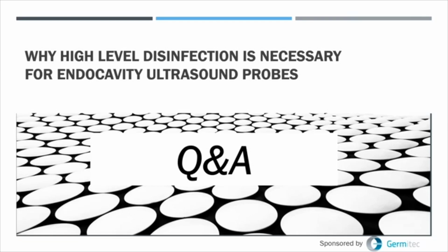The way those studies are done looking at probe covers, there are a variety of techniques one can use. One would be, if it's something like a condom cover, just take it off. You can fill it with water and look for small leaks. If it's a more solid material, you can use various methods such as filling the probe cover with electrolyzed water and then using technology looking for ions and others. So probe covers, even though they're not visibly leaking or have holes in them, often will tear or leak.